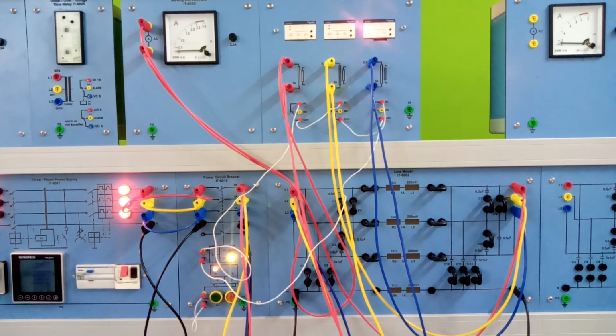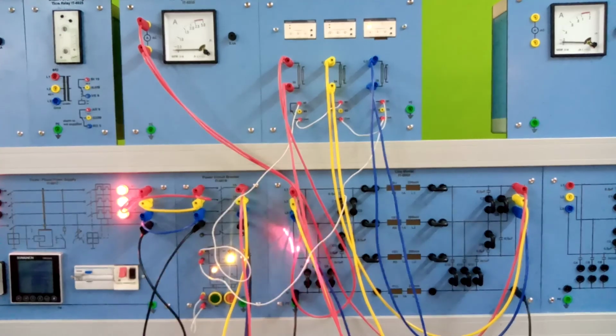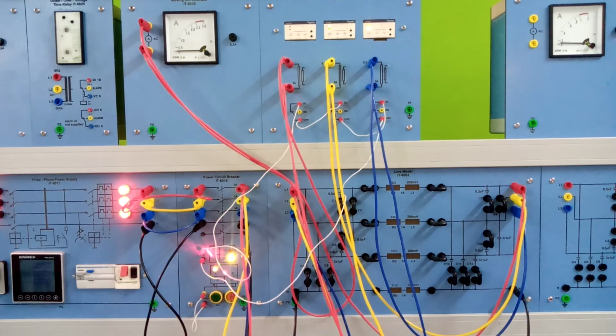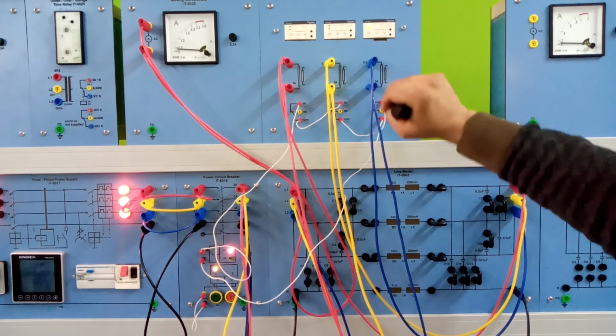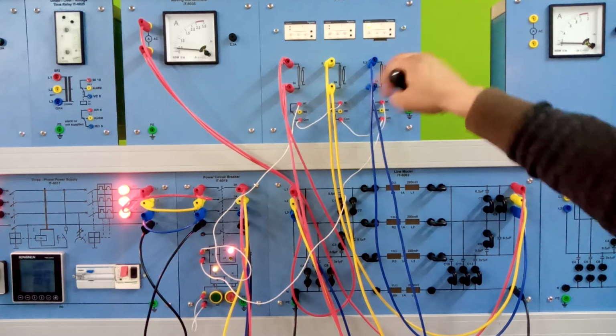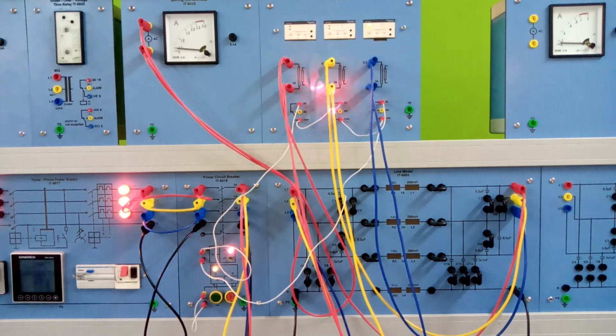You see that only the blue phase tripped, but all the other relays have been turned off because the power circuit breaker is off. Coming back towards the normal condition, I just reset this one and everything has been reset, because these two were not operated, they were just turned off by the system.